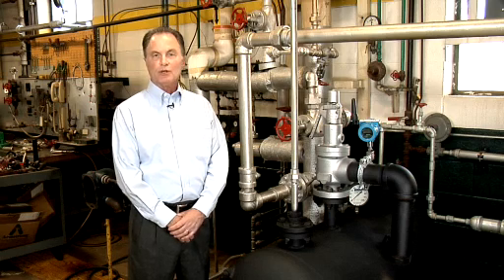As you can see from the screen, when we had a very low flow weep of the valve, we saw a slight increase in the count level. But then as the volume increased and we had more flow through the relief valve, we completely saturated the count up to a maximum of 255.